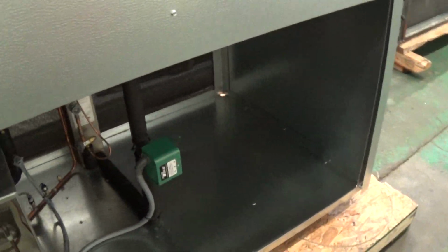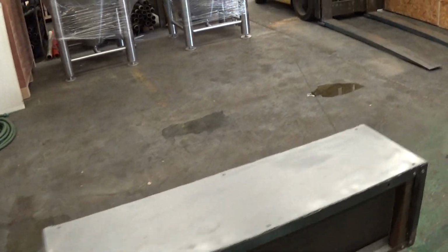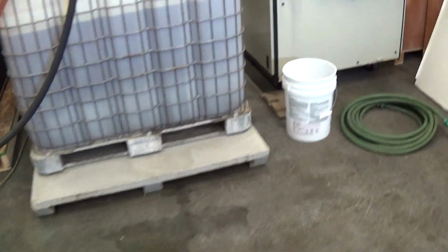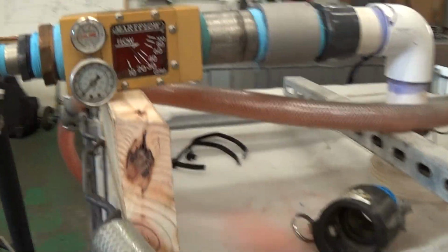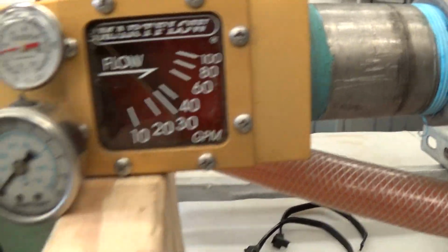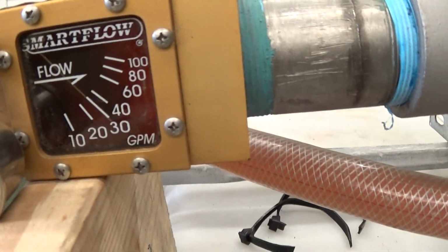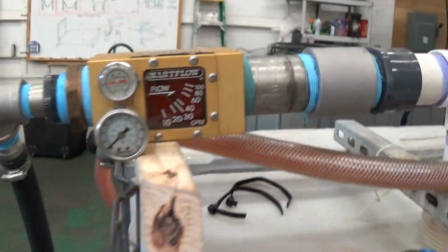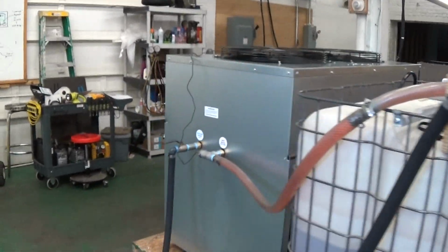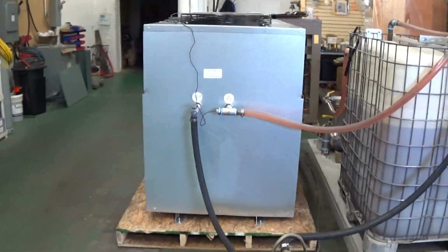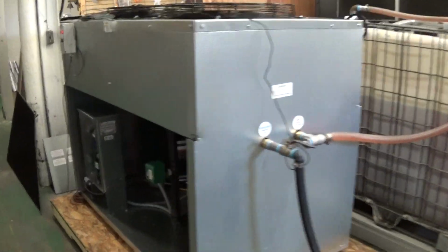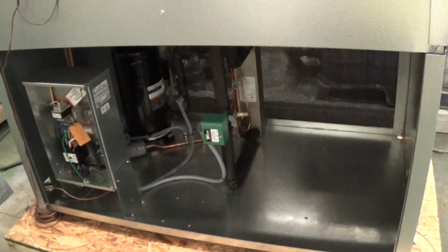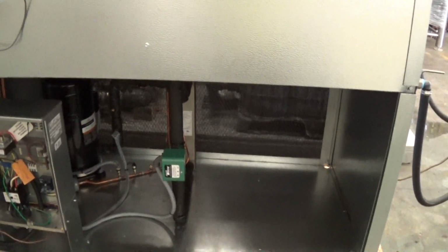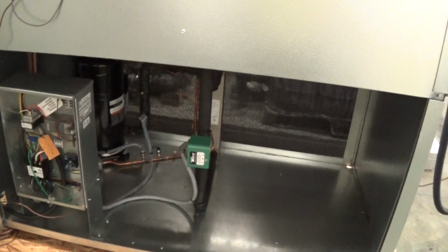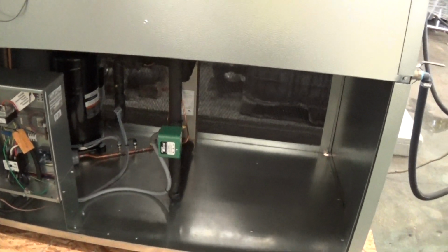As mentioned, we do have a mechanical flow switch here. In this case, we go over to our test tank. Let's see what we're getting for GPM. We're right about between, you can see that line there. We're just under 30. The units are tested and optimized at 2.4 GPM per ton, so something like this, about 24 GPM. If you get much lower than that, the flow switch will trip and shut the unit down, which is what you want. It's a safety. You need to make sure you always maintain good flow going through that heat exchanger.